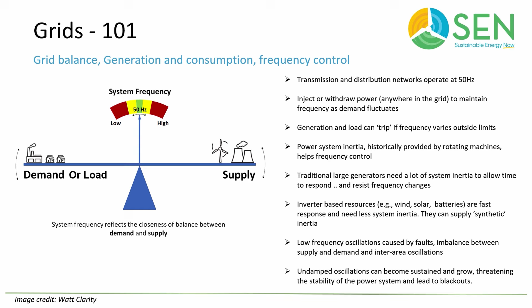Inverter-based resources like wind, solar and batteries can produce synthetic inertia using power electronics and control algorithms to inject or absorb power during a disturbance to help stabilize system frequency. One phenomenon, which I think Carlos is going to talk about, is low-frequency oscillations. They're actually a feature of the grid caused by faults or imbalances between supply and demand. Grid designs include means to dampen those oscillations using power system stabilizers. But undamped oscillations can become sustained and grow and threaten the stability of a power system, and can lead, and have led, to blackouts in the past.